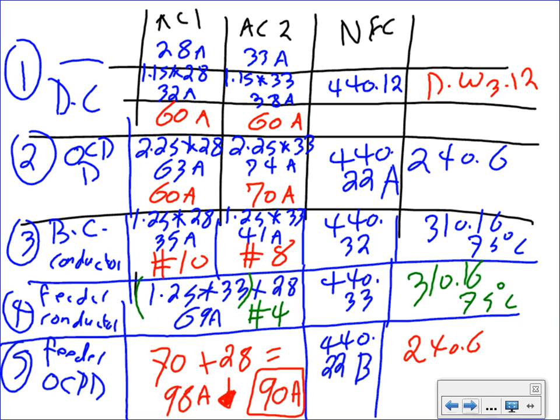Plus the sum. Now the 70 here plus 28. That's why they use the term branch circuit selection current or rated load currents. Think of it as a full load current. They keep playing with this terminology, rated and branch circuit. They have two terms that they use.